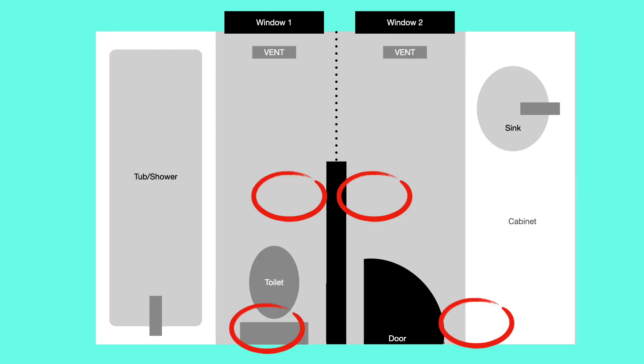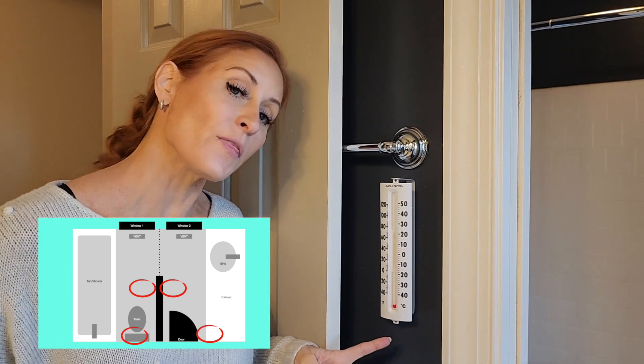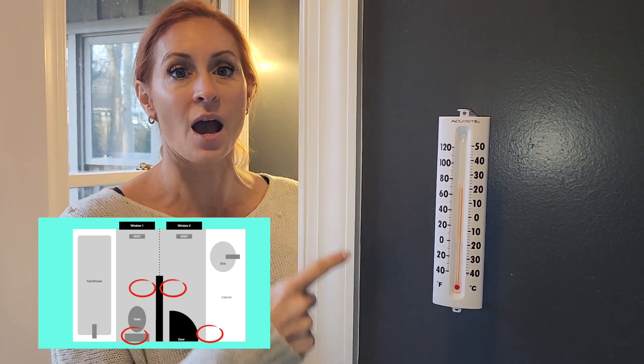I have a thermometer on the outside recording the outside temperature, and four thermometers inside. The first is on the back wall of the sink room, the second on the back wall of the shower side, the third on the partition wall, and the fourth directly opposite on the other side of the partition wall. I'm keeping the door open the whole time because when I kept it closed it wasn't an accurate representation of how it felt in the rest of the house — the two vents were blasting air and sun was heating the space differently.